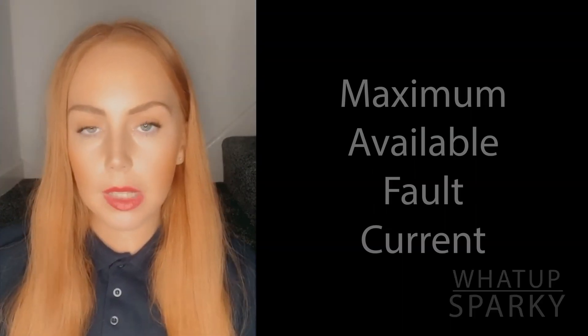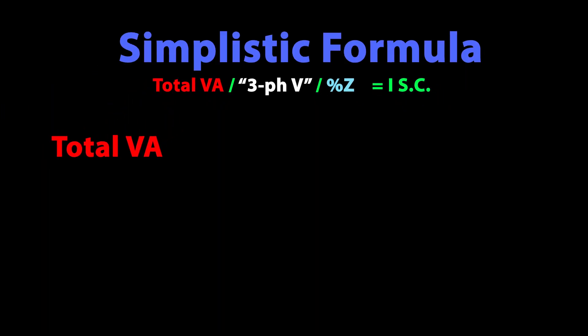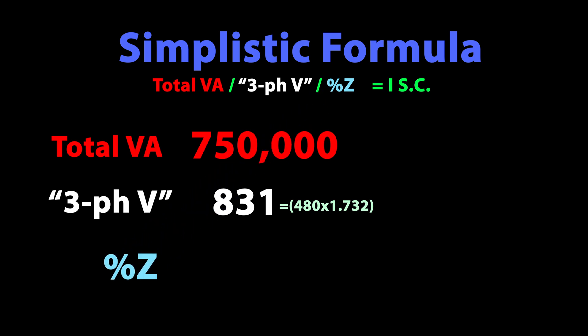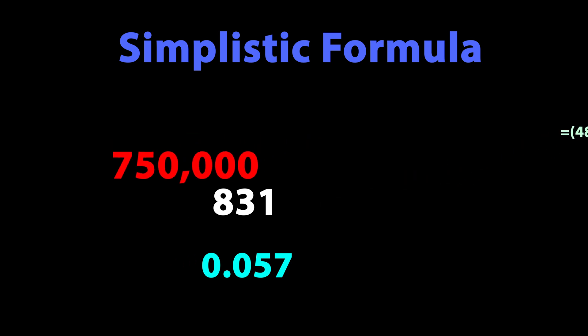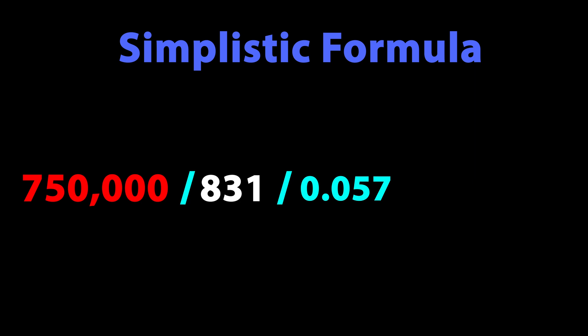Charlotte shows us the formula: for maximum available fault current from a transformer using three-phase, you need three numbers. First, total VA — in this case 750,000. Second, secondary voltage adjusted for three-phase: 831. Third, the transformer impedance — 5.7%, written as 0.057. The formula: 750,000 VA ÷ 831 ÷ 0.057 = approximately 15,833 amps — that's the conservative maximum available fault current on the secondary side. And it truly is a simple formula.